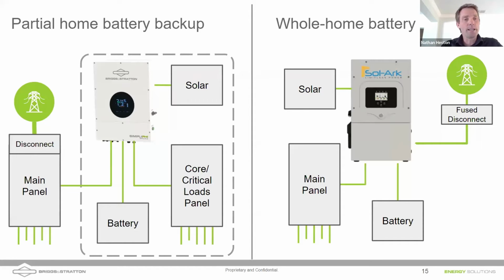So the inverter will isolate itself from the main loads panel, and so you're only backing up a portion of the home. If you do have a battery, then that battery is able to keep that AC signal alive. If we have a grid forming inverter like the small Briggs & Stratton 6K inverter there, then you could back up the core loads to the house. Maybe you want to back up the internet. Maybe you would like to back up your lights, etc.